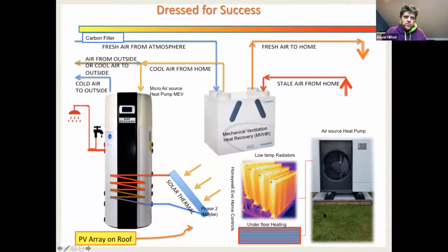So with regard to that, you can then control your heating and you can say, I want the bedroom number 1 to have a temperature of 21 degrees. It will then turn the heating, the valve, open until you get to 21 degrees and then turn it off at that point. It's not the Hive system that turns your boiler on and off. It's controlling each room. And that makes a huge difference. Zone control, mammothly huge difference on it.